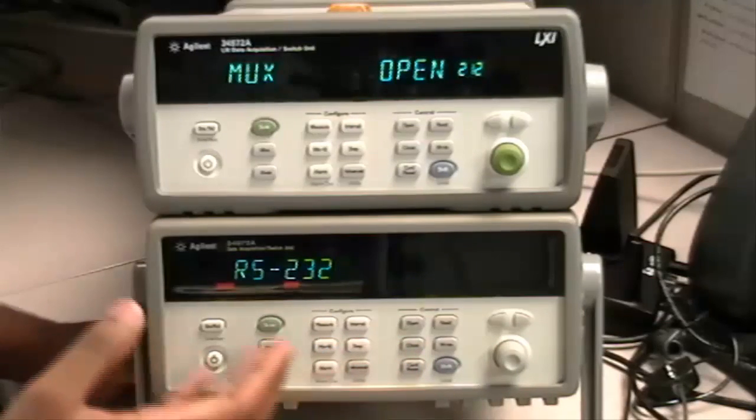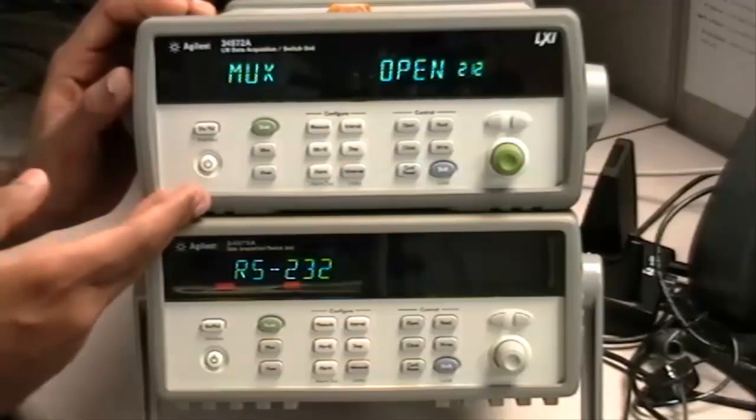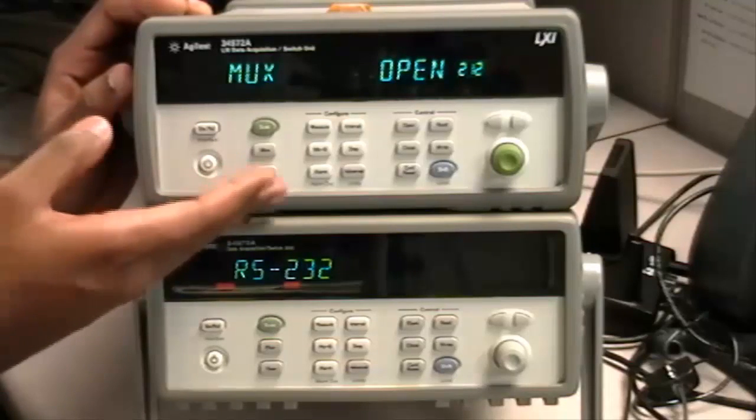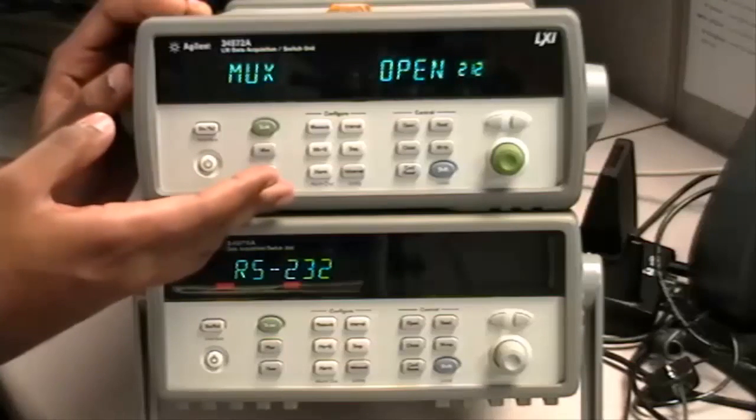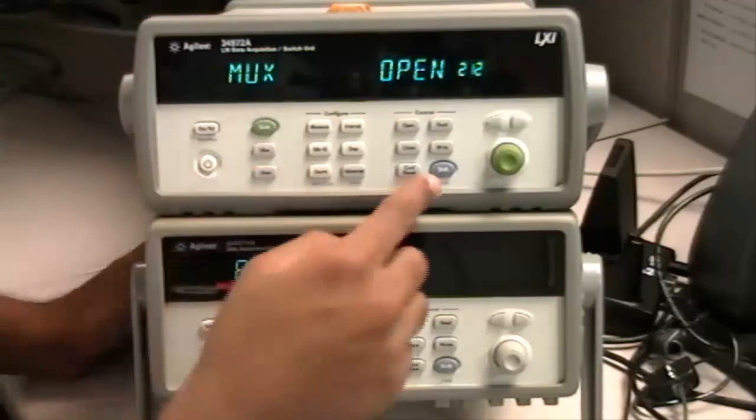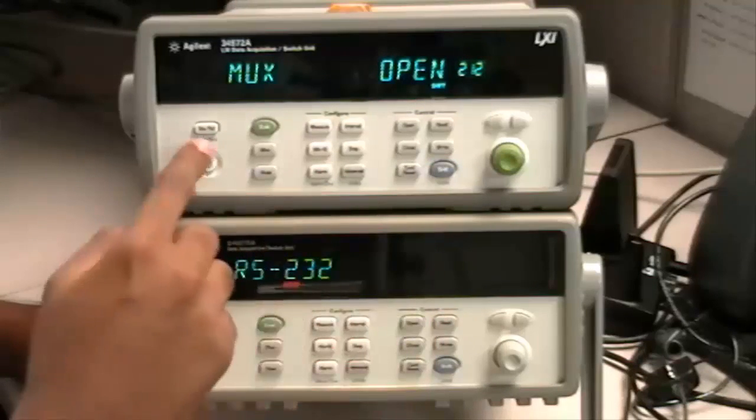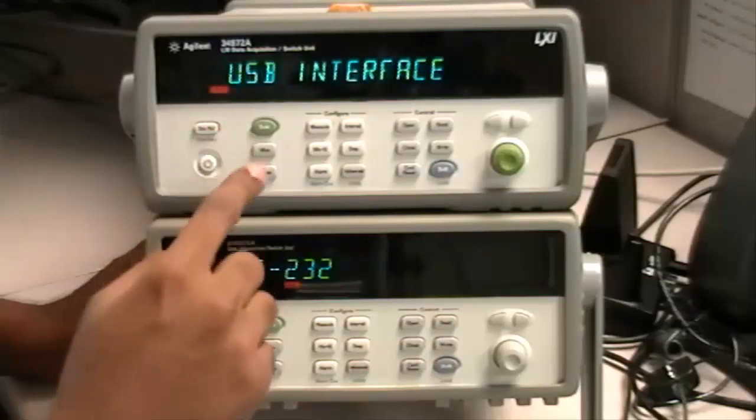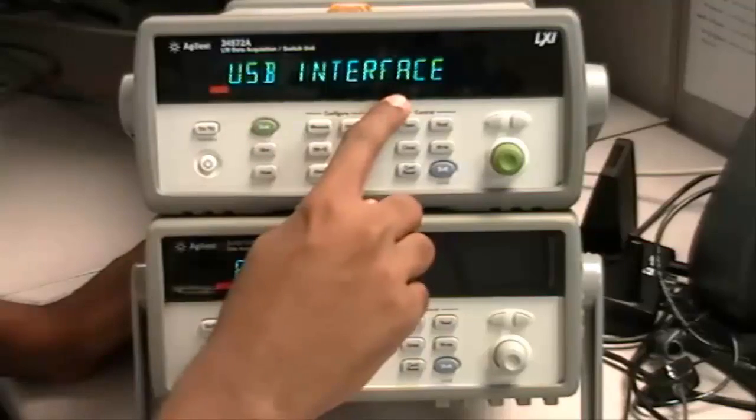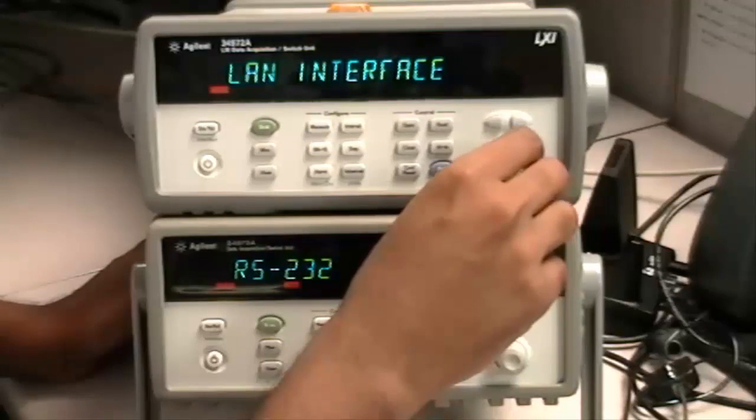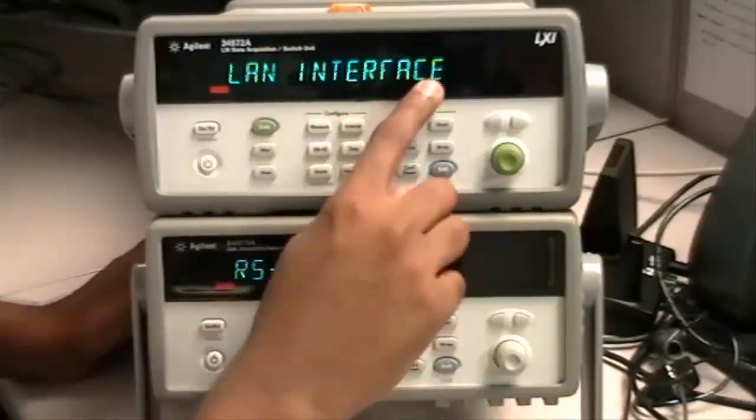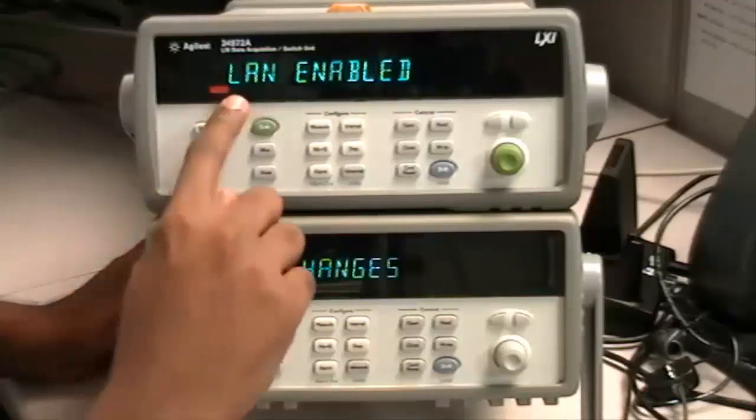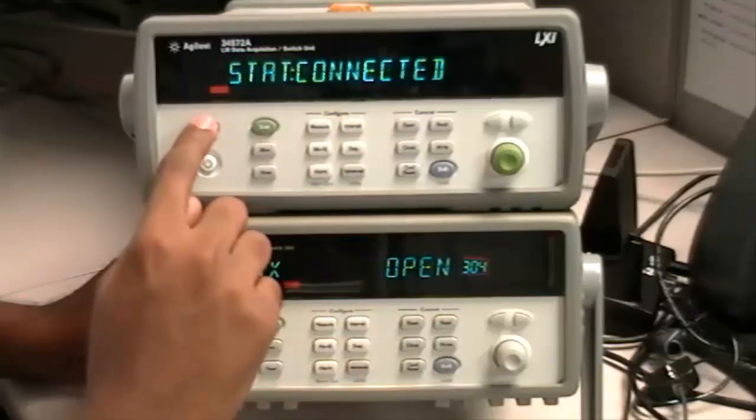Next, let's set up LAN interface on the 34972A. You hit the same Shift Local button and Store Recall. Right now it's set to USB interface, so switch it to LAN interface. Hit Store Recall. Make sure it's enabled. It's showing that it's enabled.